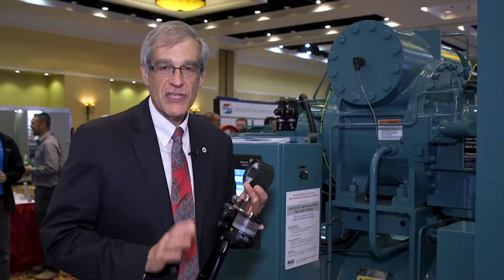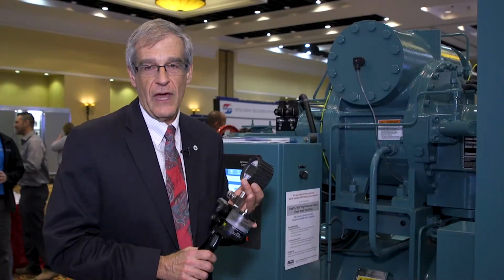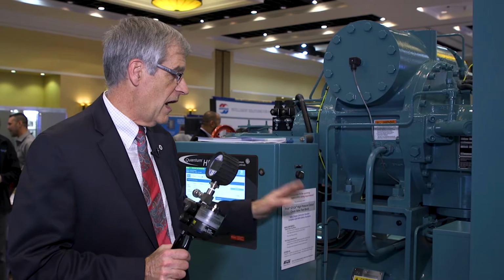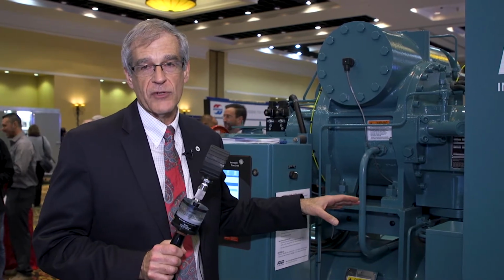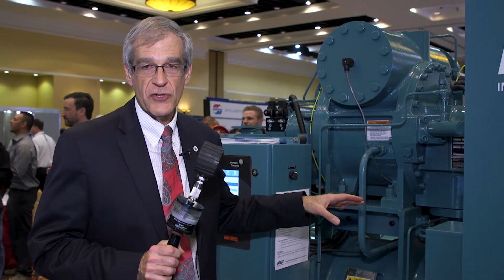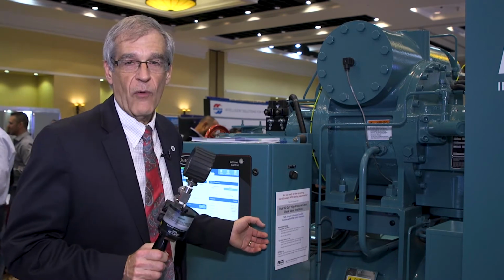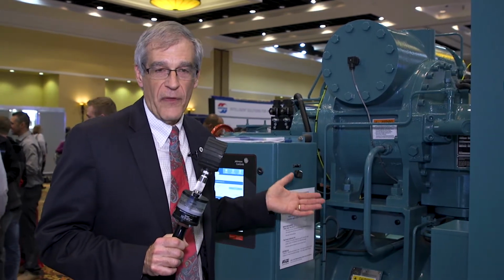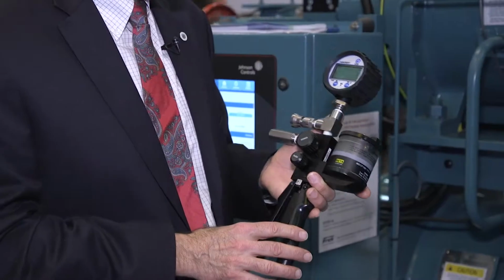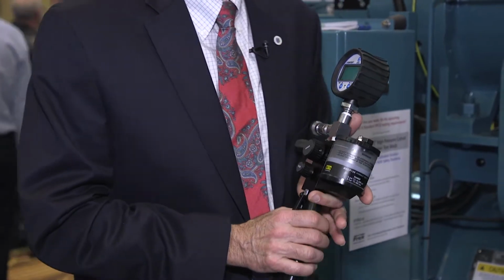This is much safer than what people typically do with testing of high pressure cutouts, where quite often they'll raise the real condensing pressure in the plant up to the cutout pressure to demonstrate that the cutout will work. The problem with that is the risk of having a relief from a safety relief valve. This allows us to do it all with oil pressure, so it's a very safe system, very simple, and very fast.